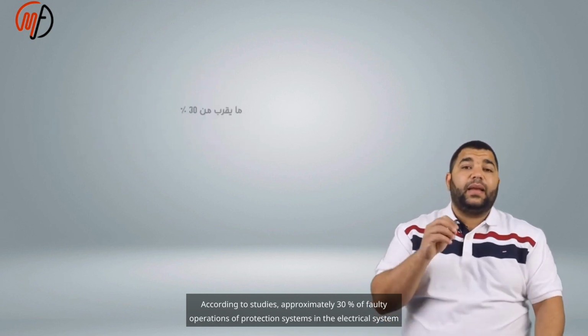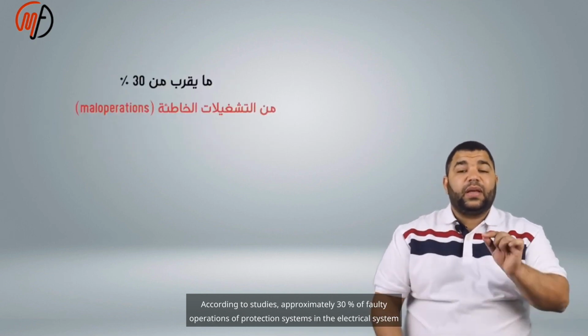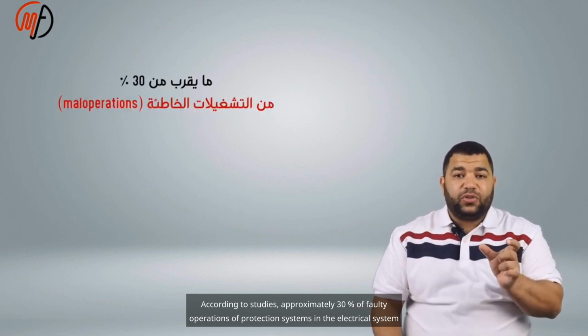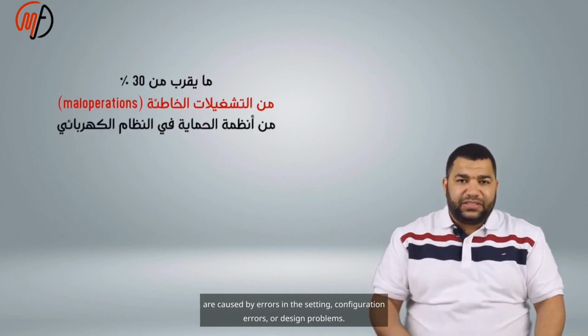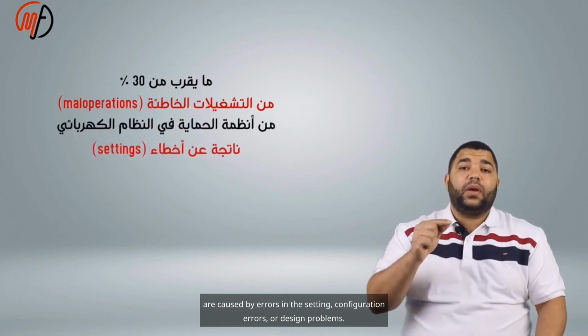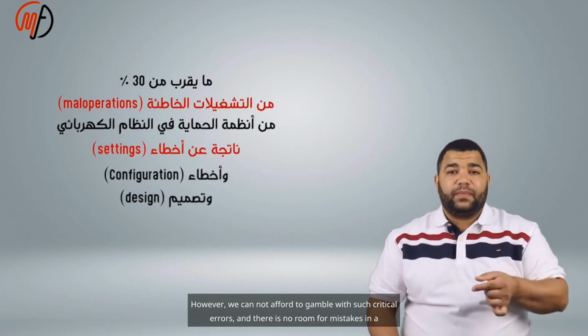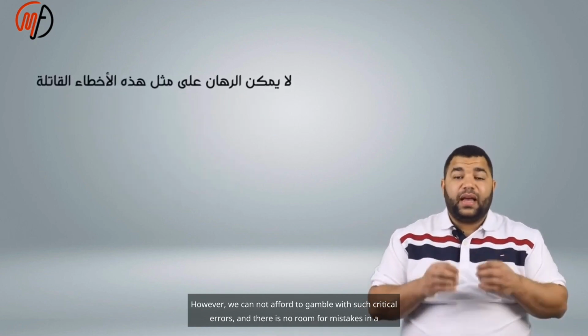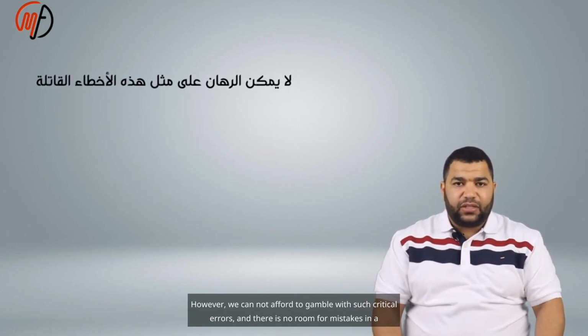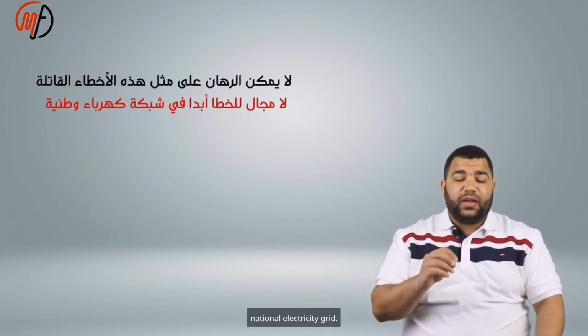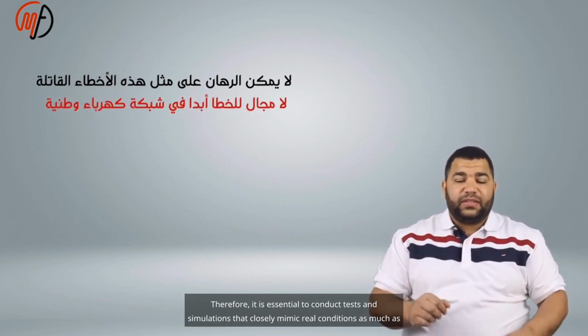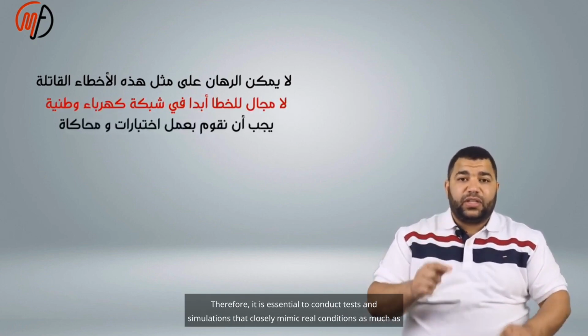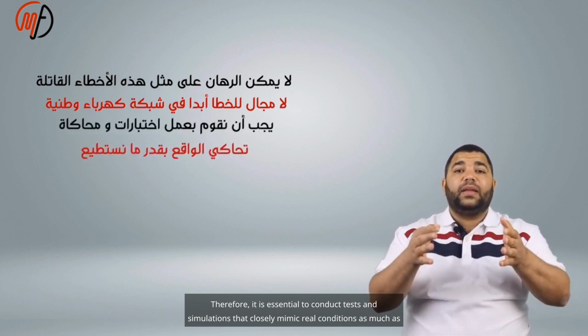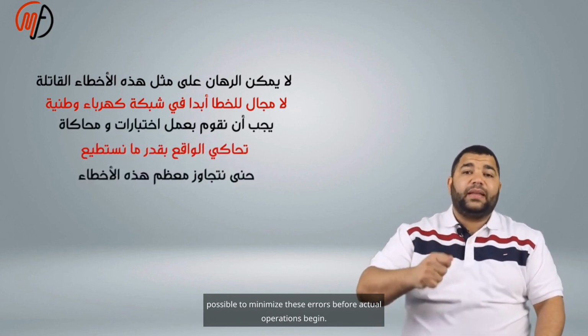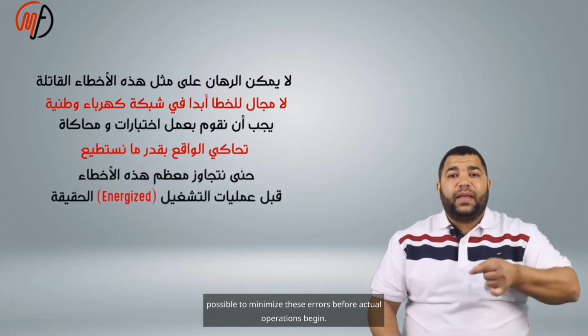According to studies, approximately 30% of faulty operations of protection systems in the electrical system are caused by errors in the setting, configuration errors, or design problems. However, we cannot afford to gamble with such critical errors, and there is no room for mistakes in a national electricity grid. Therefore, it is essential to conduct tests and simulations that closely mimic real conditions as much as possible to minimize these errors before actual operations begin.